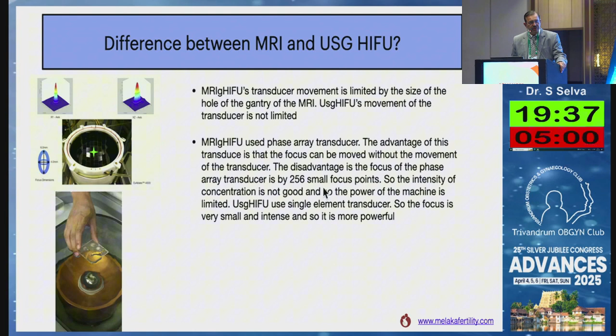So it is not one area, but the focus moves, and because of that, the power of the machine is not as strong as that of an ultrasound-based HIFU, which only uses one transducer, and you can concentrate the energy at a very high energy level. So because of this small focus, when you're doing an MRI-based HIFU, you have to give each area sonication, which lasts for 10 to 20 seconds, as opposed to second-by-second ablation when you use an ultrasound-based HIFU.